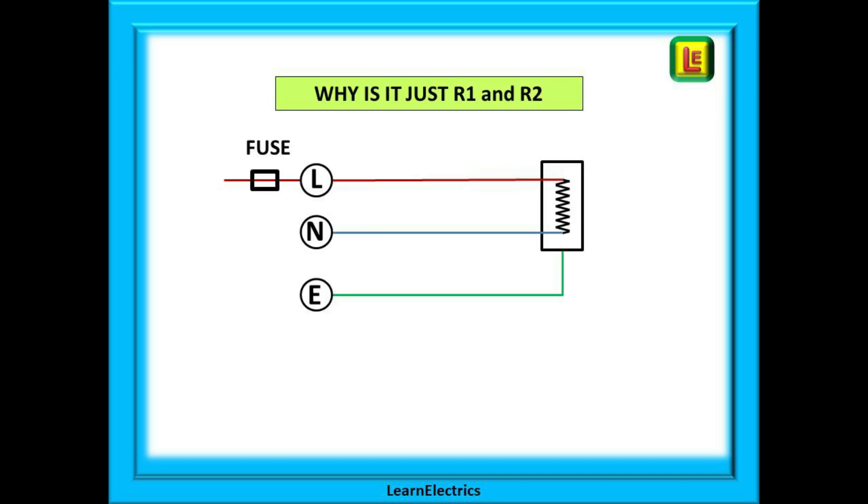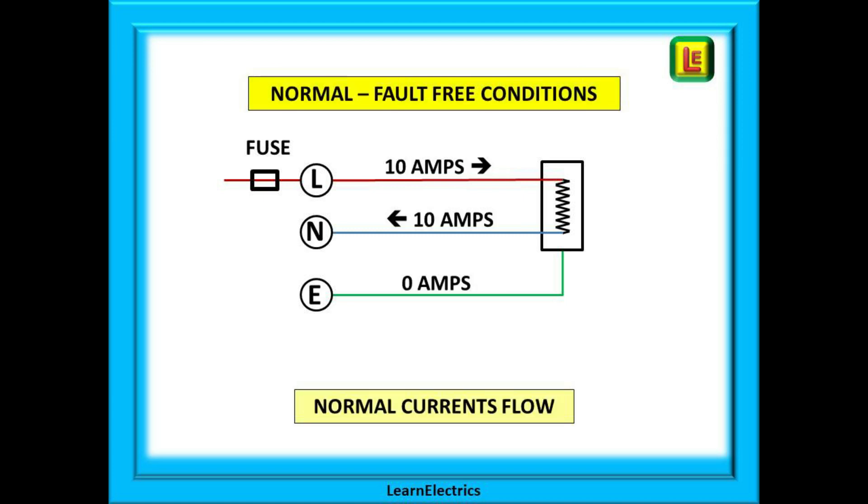But wait, you say, why is it just R1 and R2? Well let's go over the conductor names again and follow what happens in no fault conditions and also during a fault. Firstly, no fault conditions. We've kept the drawing simple and uncomplicated. We have a water heater circuit and when switched on it draws 10 amps. The energized electricity flows through the fuse and along the phase wire marked L.